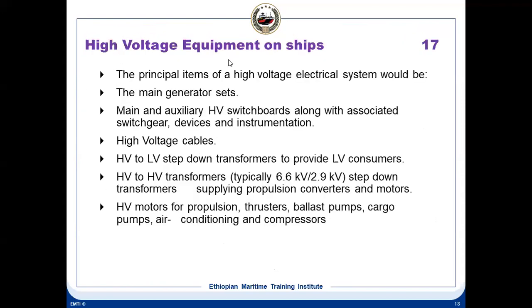High voltage equipment on ships. The principal items of high voltage electrical equipment would be like the main generator. So what are the equipments which are high voltage? The main generator for the production, that is the generator itself. Then you have main and auxiliary HV switchboards. You can have a main switchboard. Generally, you will find this basically on gas ships, where you have a cargo switchboard also. That is why it says auxiliary also. So main switchboard means from the generator it is coming to the main switchboard, and also you have some auxiliary switchboards along with associated switchgear, devices, instrumentation.